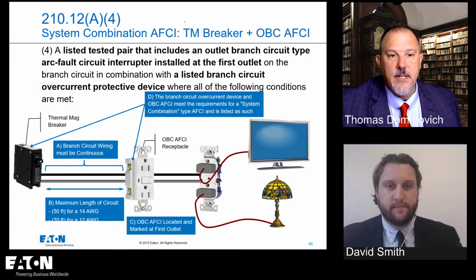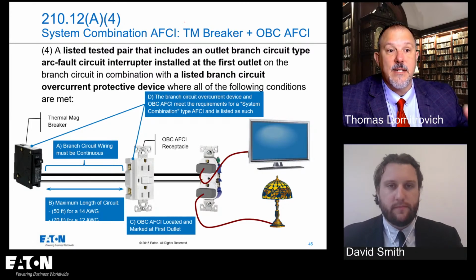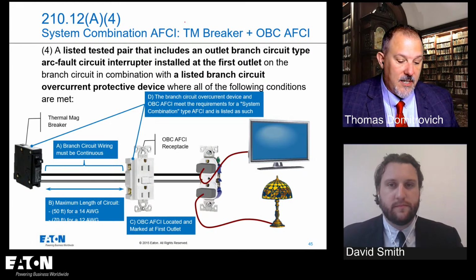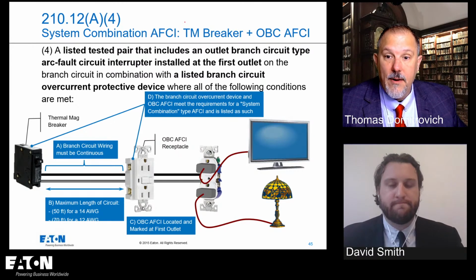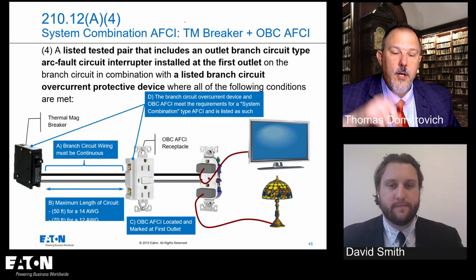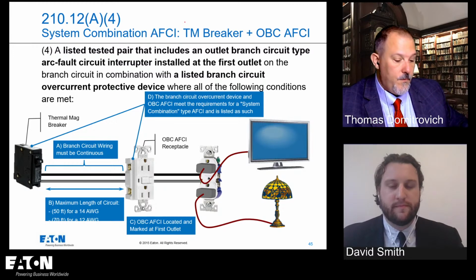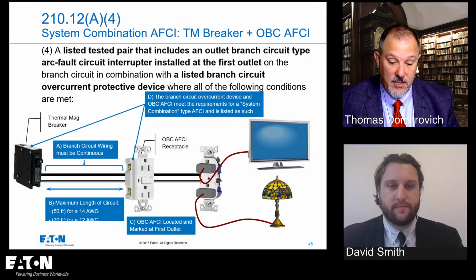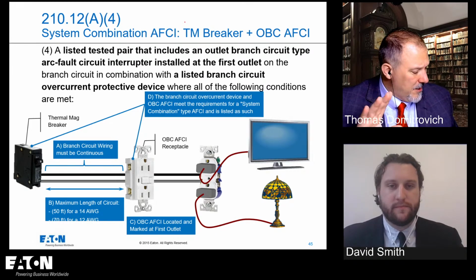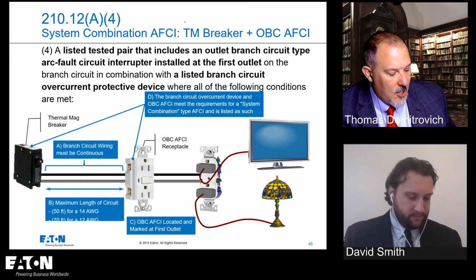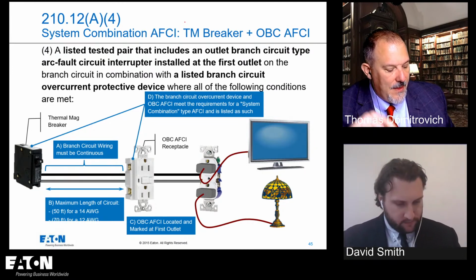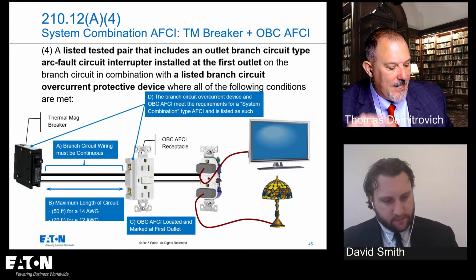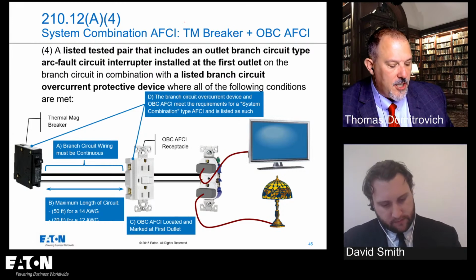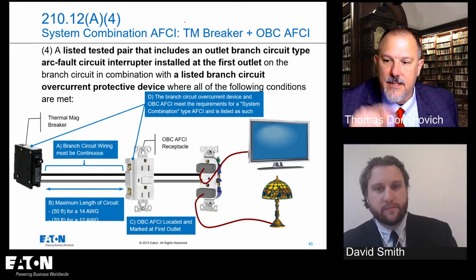And then 4 was put in because they wanted the OBC to be able to be put down with say a standard thermomagnetic breaker. It wasn't an electronic device, but based upon all of the data, that's almost impossible without having issues. So for list item 4, over the years this has changed a little bit. I don't think it's changed really. It says the combination of the branch circuit overcurrent device and outlet branch circuit AFCI shall be identified as meeting the requirements for a system combination type AFCI and be listed as such.